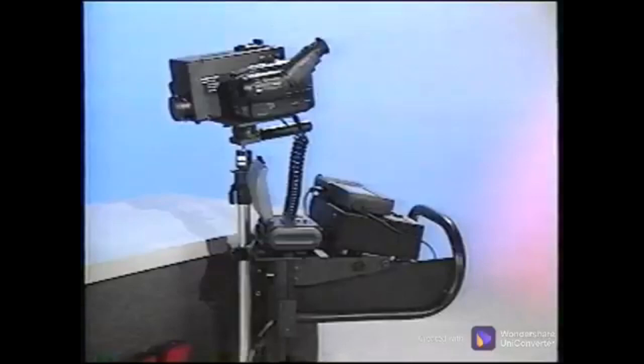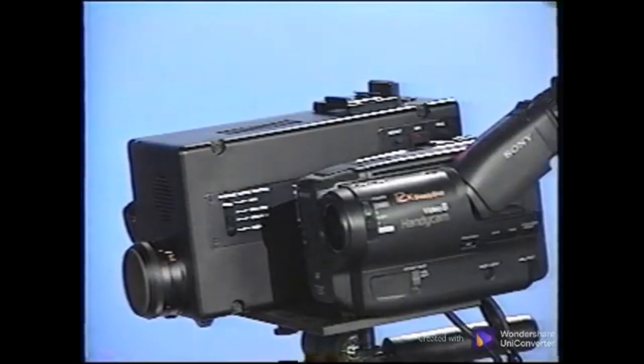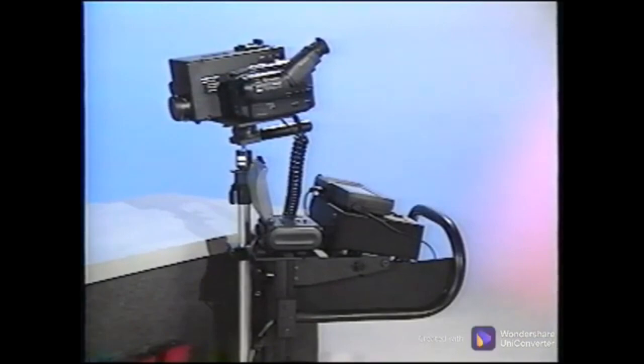The goal of a thermographer is to detect heat differentials and determine specific temperatures. With a good quality camera, temperatures can be determined within a tenth of a degree. The camera system we are using here, and for most of the images used in this program, is the CSI Model 9000 thermography camera. It uses a thermography camera with the focal plane array technology, which can be used as a standalone unit. This system uses three other components that are needed primarily for documenting and reporting.